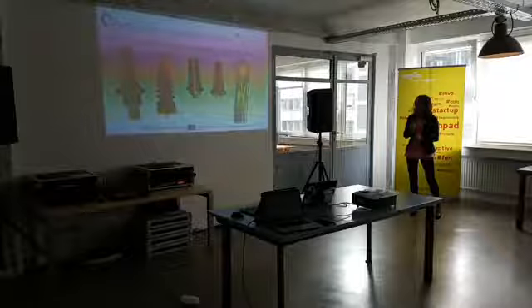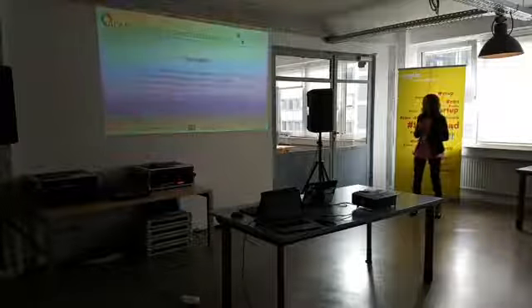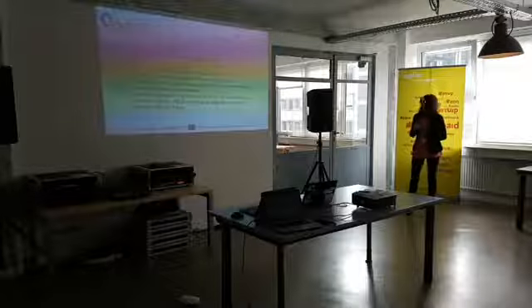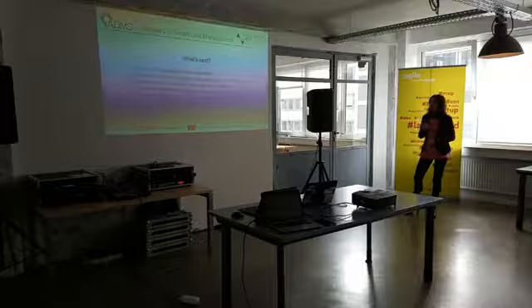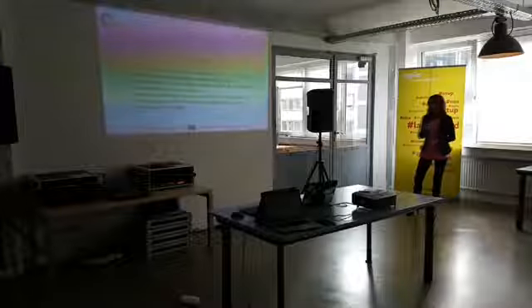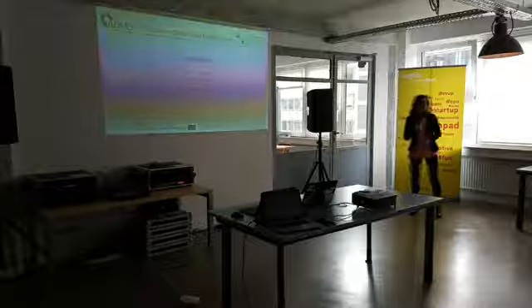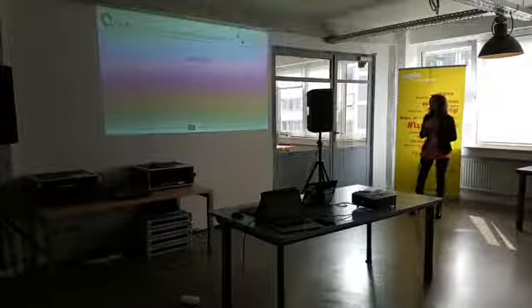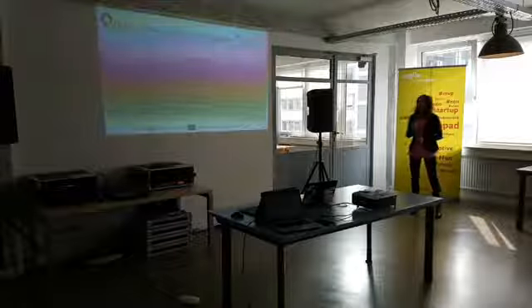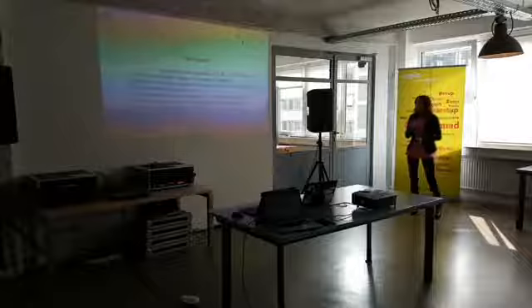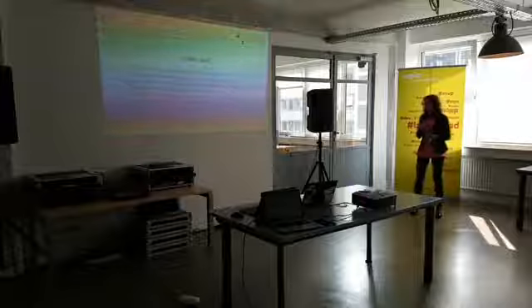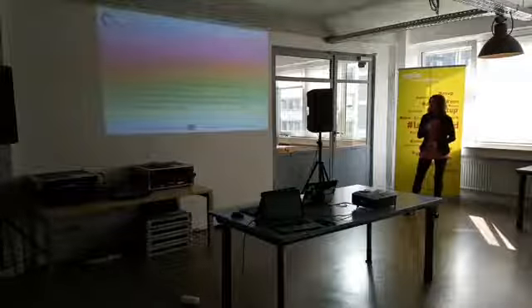This is just an example to give an idea of how it is installed. So what's next? We know that next year, E-Distribuzione, the Italian DSO, will start installing low power instrument transformers also in primary substations, whereas in secondary substations they already installed sensors instead of transformers. Presently, the IEC is working on a new standard relevant to sensors embedded into existing equipment, as I showed previously - so not standalone sensors.